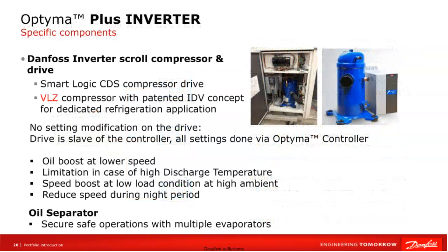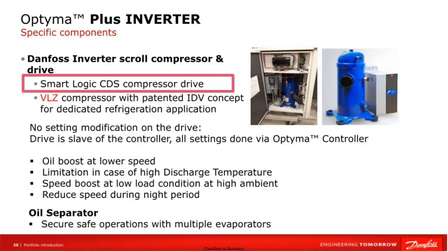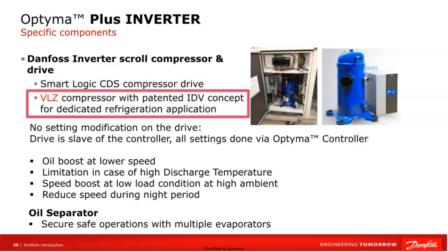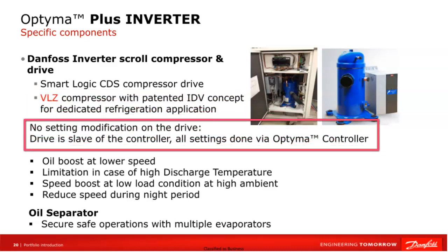The heart of the Optyma inverter unit is an advanced Danfoss scroll compressor combined with the intelligent inverter. This synergy is based on the intelligent CDS drive logic and the special VLZ compressor, which was developed significantly for refrigeration applications and equipped with a patented IDV technology. What is extremely beneficial about this cooperation is the fact that you do not need to make any changes in the inverter settings. The inverter works as a slave, and all configurations are made via Optyma controller.